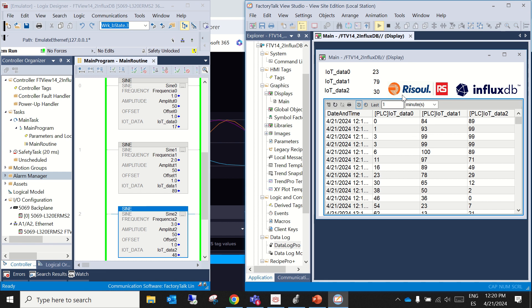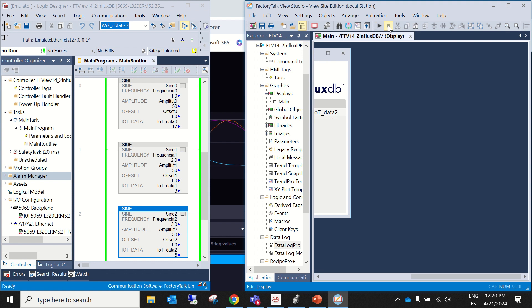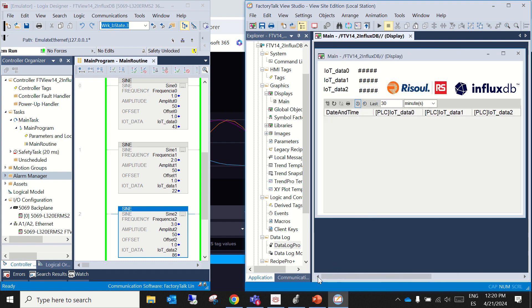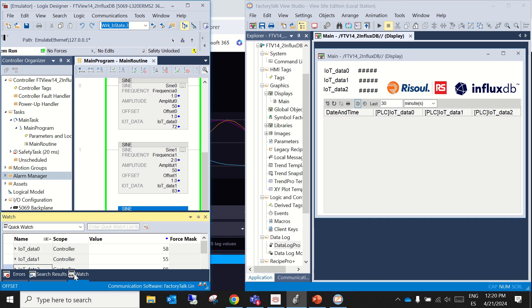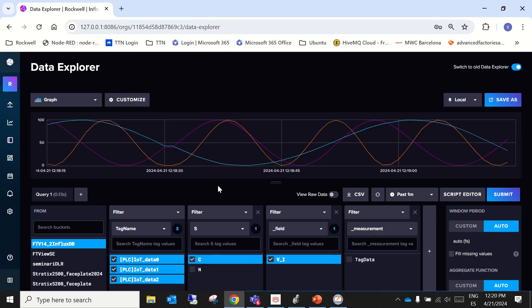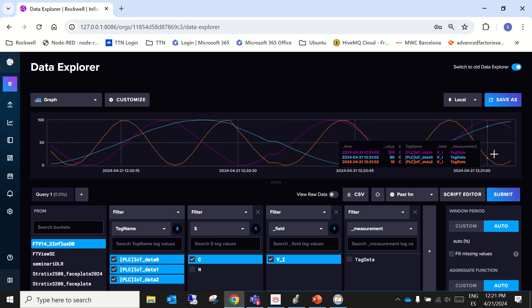This runs as a service, so even if you stop the HMI or the SCADA faceplate, since the PLC is still running, the service continues storing data in the background, as you can see here.